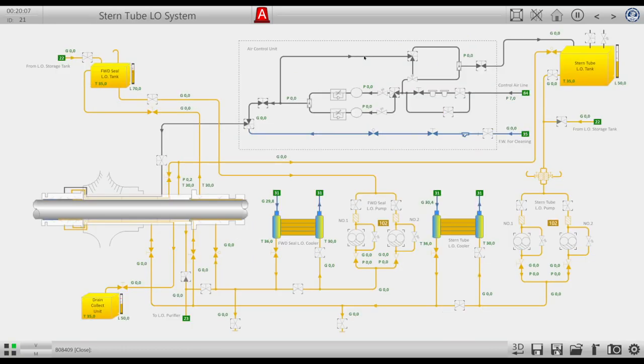If we check back again, we now have pressure from the lubrication oil. This was the first part of lubrication. The second part is using the lubrication oil to make a seal around the main shaft. Let's prepare that one. Using this gravity tank, via this pump, this cooler if needed, over there. So we have a closed circuit, we can start this pump. Match the pressures. And the second part, and these valves also via heat exchanger, going to this part, starting that pump. And we also have a flow. So now we have lubrication all around the main shaft.